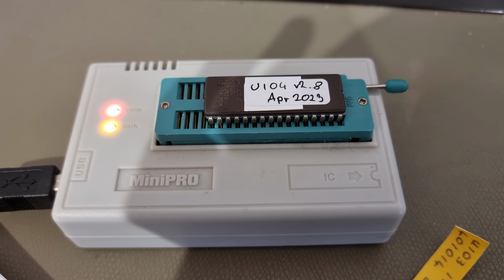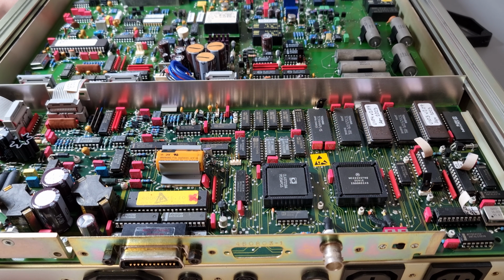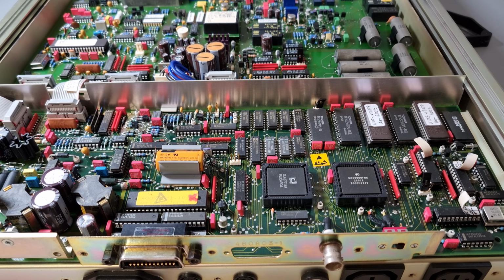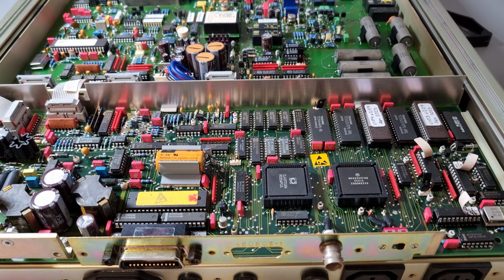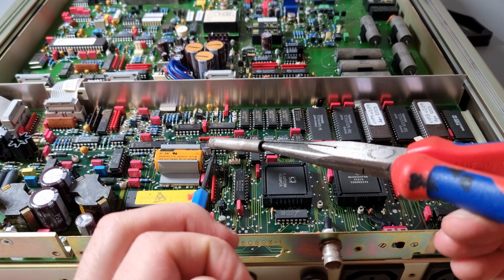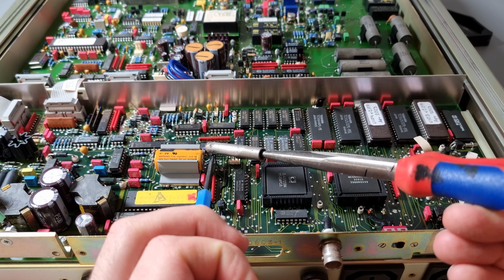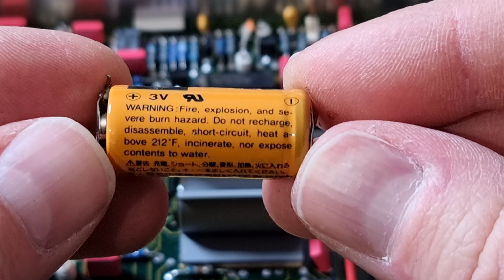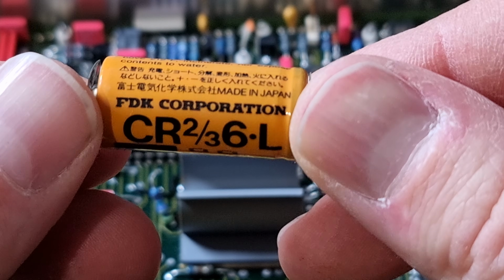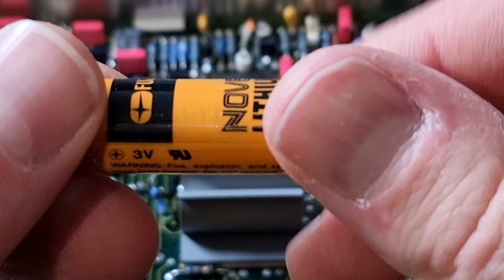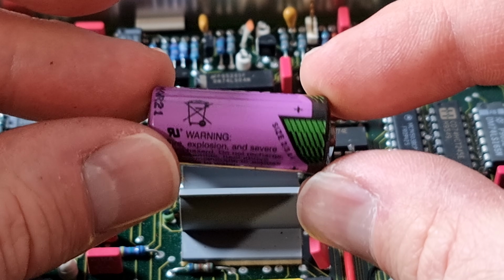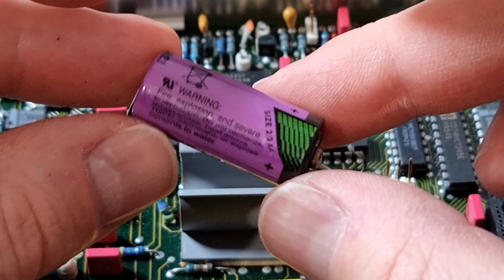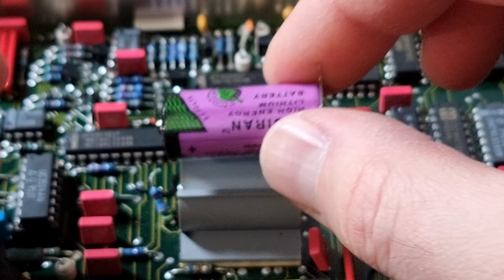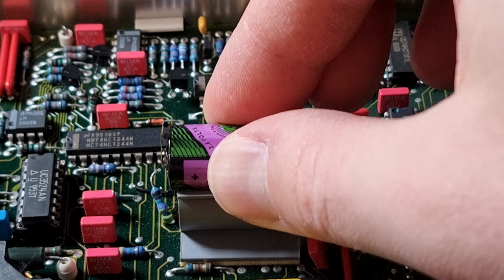The very valuable calibration constants are stored in volatile memory, which is made non-volatile with that 3-volt lithium battery. To avoid losing anything, I will swap this battery with a powered-on instrument and an isolated soldering iron. The latest date codes I'm seeing in here are around 1995. The 00 marking on this lithium cell might mean that it was swapped around year 2000, so in a 5-year interval, precisely as per manufacturer recommendation. This swap just now is a teeny tiny little bit overdue though. We are around 18 years too late. Oh well, as long as the data survived.